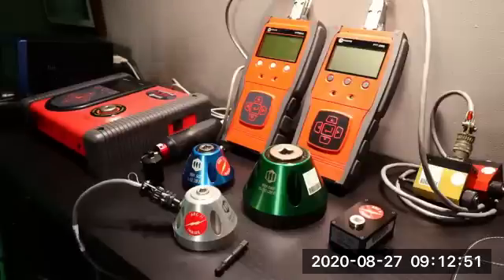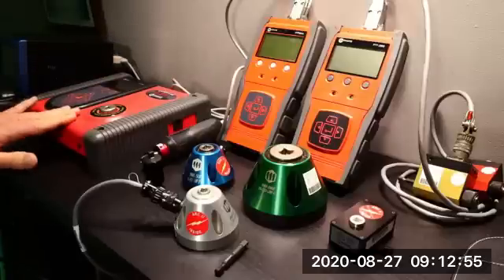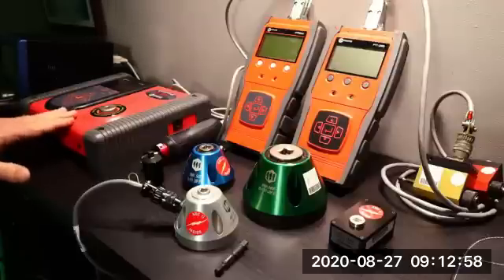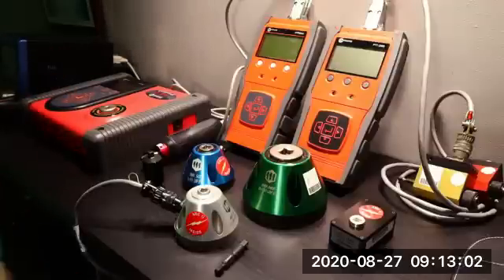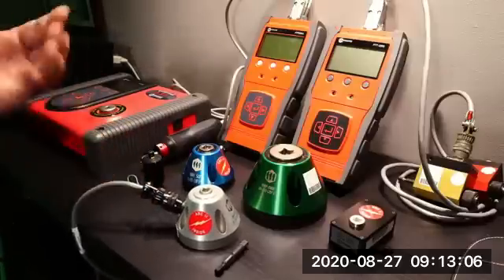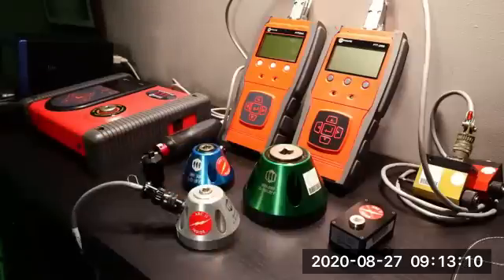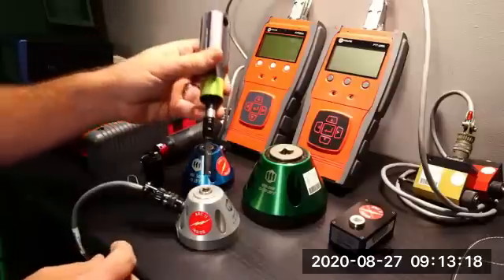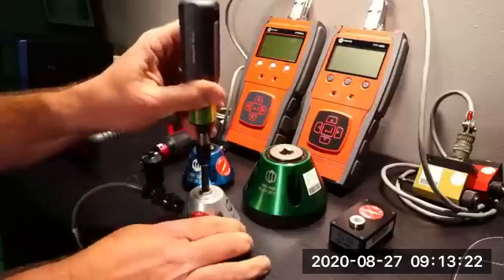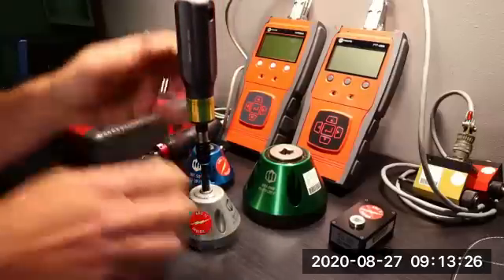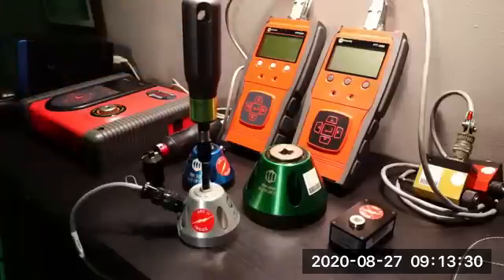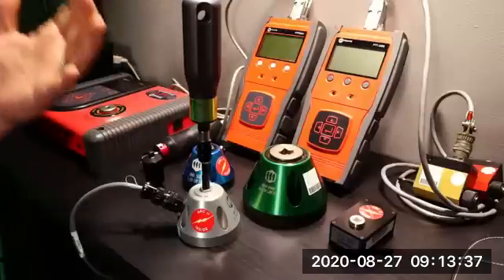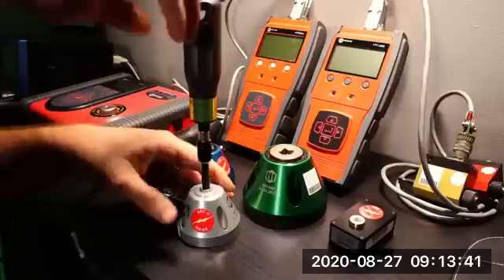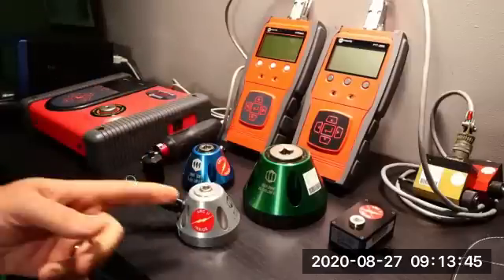So currently I have this sensor paired to this torque analyzer, our LTT product. Unfortunately, you can't see the screen, but that's okay. I don't have the analyzer itself bolted down, but I can show you basically how we would use this to calibrate our tools, like a torque screwdriver here. In this case, I can take the square drive and go straight into the analyzer. If I cam over the wrench, we're going to see our reading on the torque analyzer, and we can make adjustments to the tool and make sure that it's within our specifications. So that can be done with hand tools directly straight into the analyzer itself.